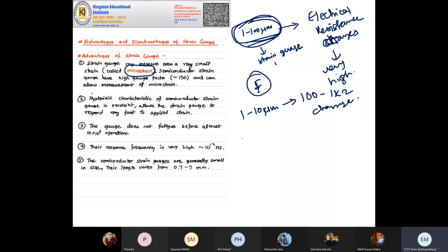strain is in the order of micro range, because the strain formula, you know? What is the unit of strain? Strain is unitless. I made a mistake earlier writing micrometer, it should be micron. If this unitless quantity is of the order of 10 to the power of minus 6, it's called microstrain, and strain gauge can measure microstrain. Another thing is strain gauge has very good hysteresis characteristics, that means it has low hysteresis.